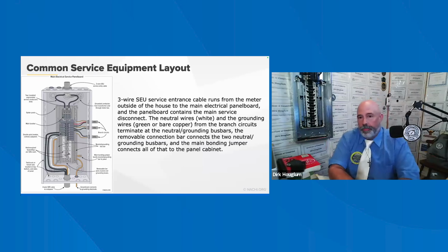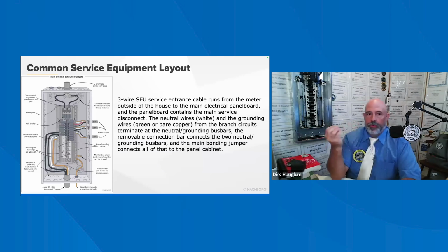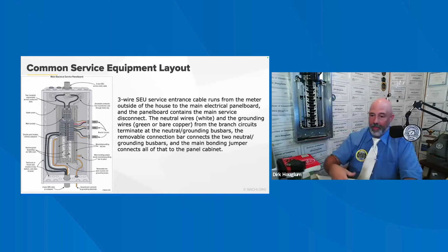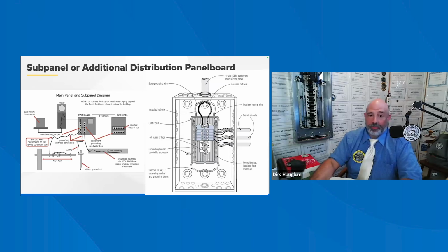Okay, depending on the time, we're going to go through this a little quicker. The 3-wire SEU service entrance cable runs from the meter outside the house into the main panel board disconnect, and the neutral wires then go into a 4-wire system downstream. Now, a common layout has the meter outside and the main disconnect on the inside. In this case, the service entrance wires run from the weatherhead through the meter and into the main disconnect. If the meter and the main disconnect are in the same enclosure, then the wires simply run from the weatherhead to the combined meter and main disconnect. Okay.